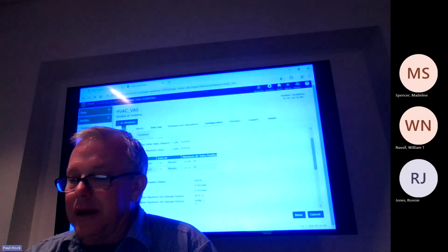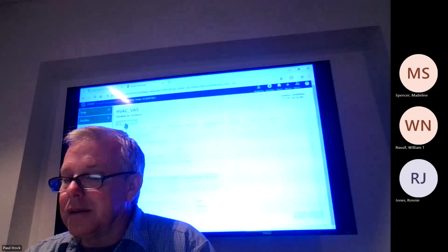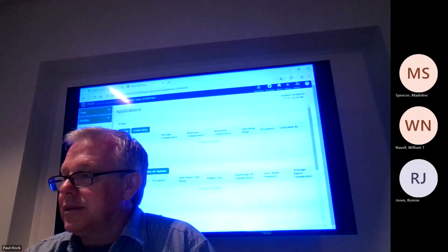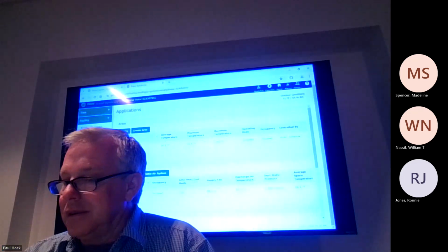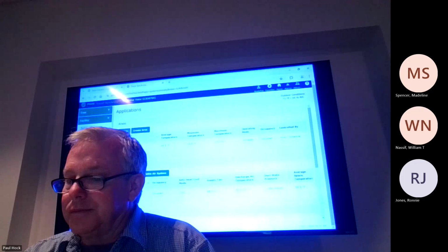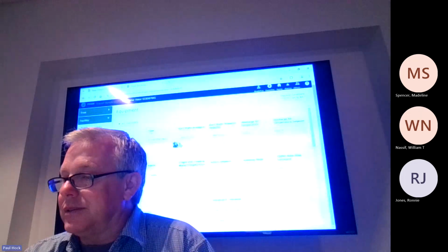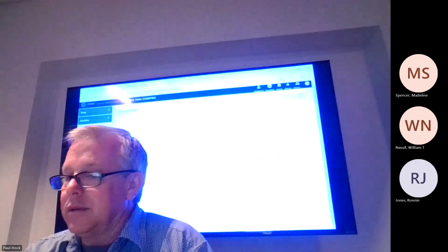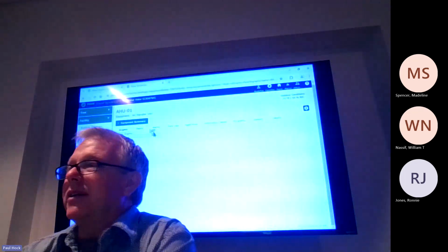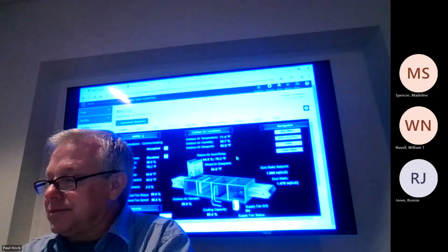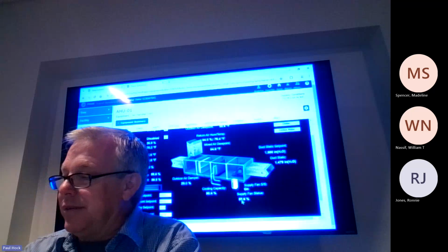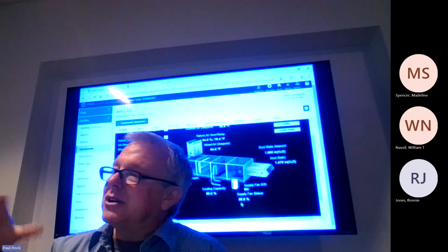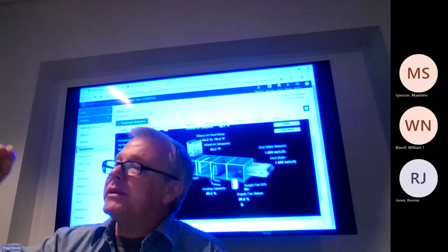And I think the fan's running pretty low right now. So it's duct static pressure. It's going to try to maintain about 1.5. Then you can pretty much get it through any device, just navigating through it. Right now the fan's only running 60% to maintain airflow. So if that box gets above 95%, starts opening up, every 15 minutes it's going to look at it and it's going to start creeping that fan speed up.